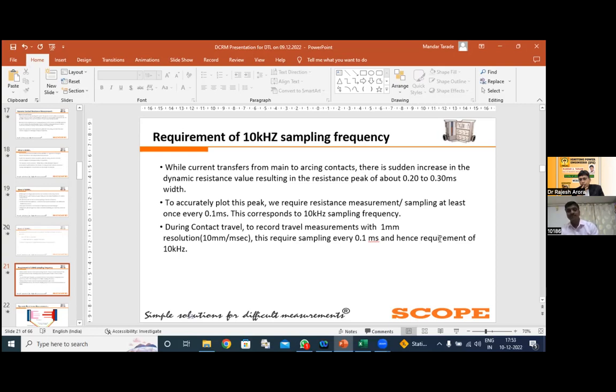Now, people may wonder why a 10 kilohertz sampling frequency is required. In simple words, the higher the sampling frequency, the better the resolution, because it reduces your step size. Also, in terms of breaker terminology, whenever you perform the DCRM operation or dual operation, when the current transfers from the main contact to the arcing contact there is a sudden, drastic increase in the resistance value. Because during commissioning itself, our static contact resistance value is around 32 to 40 micro ohm, whereas our arcing contact value is around 500 to 550 micro ohm.